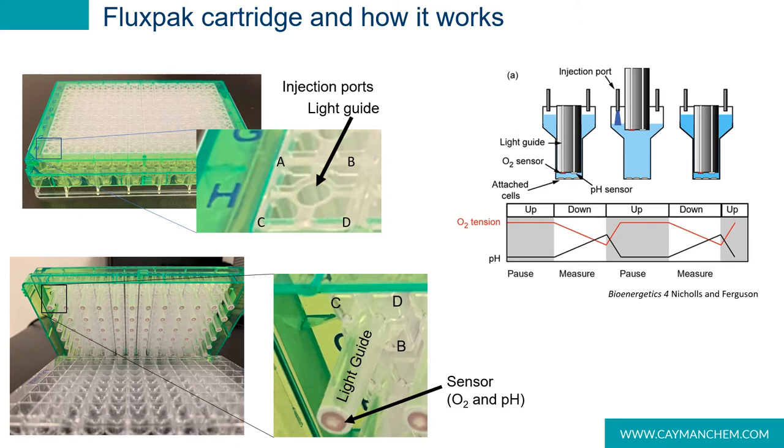This facilitates mixing following injections. Before an assay can be performed, the Fluxpak must first be hydrated, typically overnight, injection wells must be filled, and the cartridge calibrated. Once calibration is complete, the utility plate is exchanged for a cell plate containing the pre-plated cells. A typical measurement cycle consists of a mix step where the piston is slowly raised and lowered, followed by a measurement step where the probes are lowered to create a measurement chamber.